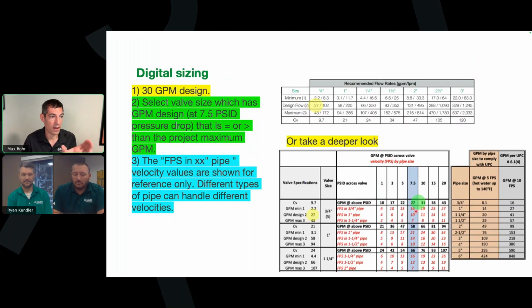And that's why you see the sizing difference between the properly sized mixing valve, which is built for that velocity. It's a control device. It has either a nickel plated brass or stainless steel ball that's okay with that high velocity, but the copper pipe in this scenario would not be. So you would want to go up to 1.5 inch pipe size for the mixed outlet. So properly sized 3/4 inch valve with 1.5 inch mixed outlet in copper to stay below that 5 feet per second seems odd, but those are the properly sized devices for this scenario.